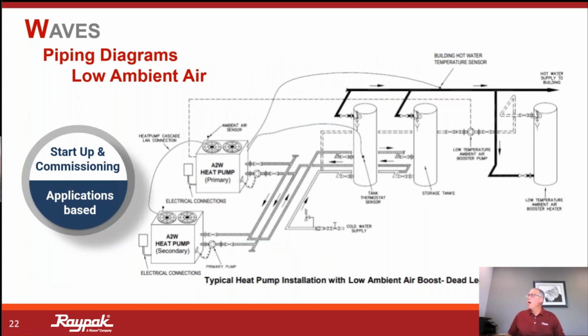And we do have one where we are looking at a low ambient air boost system, where we would have a booster heater, typically electric. You will see that this is circulating between the heat pump and our primary storage tanks, just like we described earlier. But now, if we get to a low ambient air temperature and we are not harvesting the necessary BTUs relative to the demand, now we have a booster heater that we can draw from that is not going right out into the system. It's actually piped in reverse series to go back into our primary storage tank.